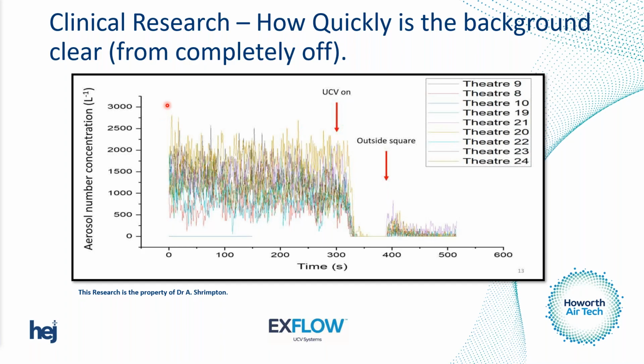So basically, at Southmead, they have the facility to control the AHU and the UCV to off. And basically what they've done is measured the background with the UCV and the AHU off, and you can see we have a high background spike, as you'd expect. And then we bring the HVAC and the UCV system on together, and the part that was staggering for me, I thought was quite quick. You can see between that point there and that point there, within about 2 minutes, we go to a background reading of almost 0. And then he's moved his particle counter outside the square, and then you start to see these sort of spikes pick up here.